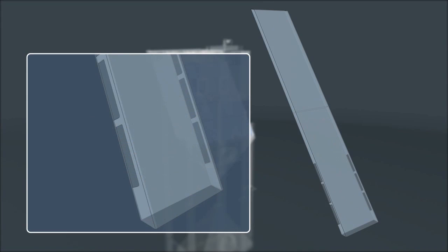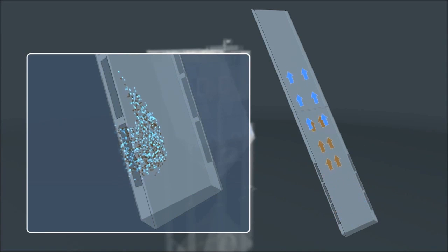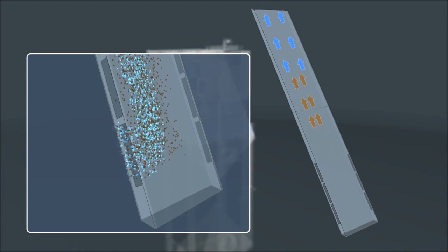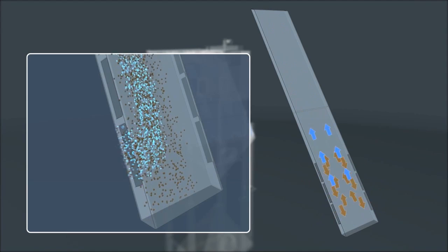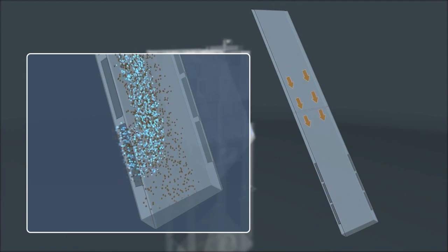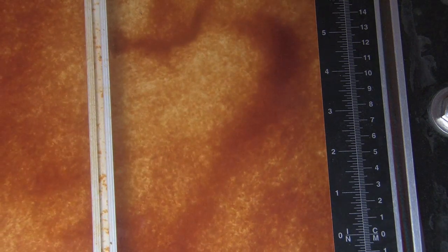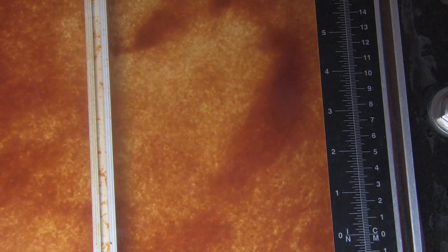In order to improve the design and allow for full utilization of the plate settling area, the feed slot location was mirror imaged to be on the bottom of the plate instead of the top. This minimized the disturbance caused to settling solids, allowing for the use of 100% of the clarification area available. Parkson performed a full-scale pilot test to validate the design and produce a comparison of the two models. This is the original 80-20 design. Here the turbulence is evident from the influent mixing with the solids traveling down the plate.